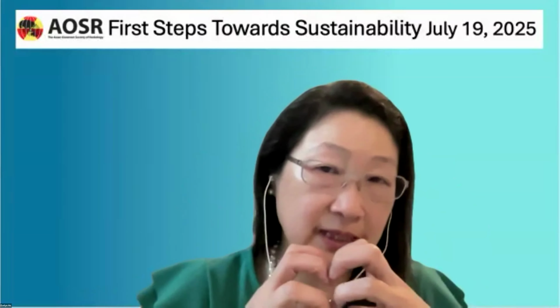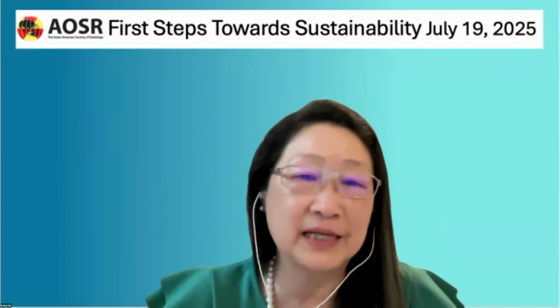So the auto shutdown that modern scanners have is really about how you automate the shutdown. Am I correct? Correct. Yeah, you cannot set a timer in the scanner. So we can still do it if we set a timer, like we do for cooking, setting how long we put something in. That's another way to get around it, a lower carbon footprint way of doing things, because many people won't be able to upgrade their scanners to the latest eco-friendly design unless they are in the buying cycle now. Thank you very much for that confirmation.